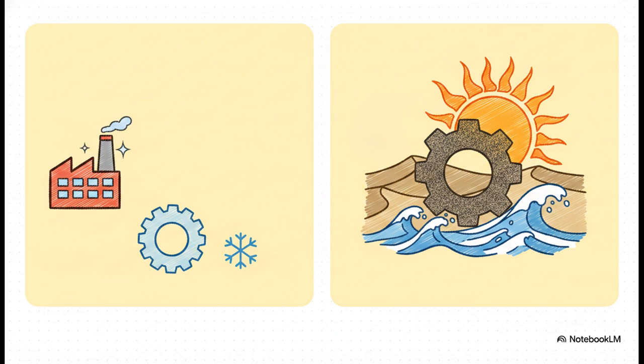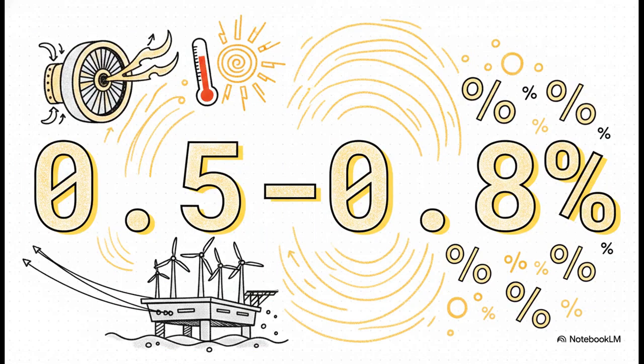Because, as it turns out, gas turbines are incredibly sensitive to ambient air temperature. And this is exactly where the derating factor kicks in, and it's a huge deal. You have to derate the turbine's power output by 0.5 to 0.8% for every single degree Celsius above that 15-degree ISO standard.